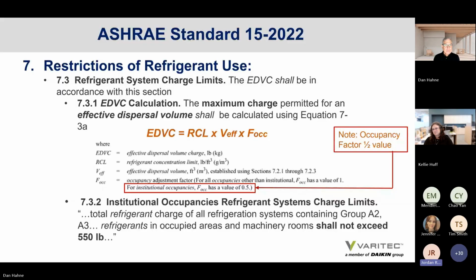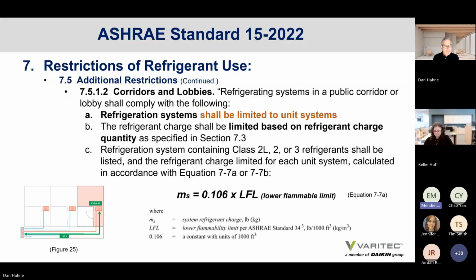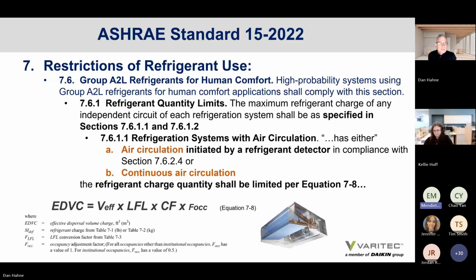I thought that there was a separate calc where the volume was derived from the LFL limit. It depends, and I don't know if you recall my last response. Sometimes whoever you need to convey this information to, to show that you're in compliance, can be in terms of volume or in terms of quantity of refrigerant. So yes, you can go back and forth, because you see the volume is there. You just need to calculate for the volume. If you want to show compliance in terms of volumes, you can use either the quantity of refrigerant or the volumes.